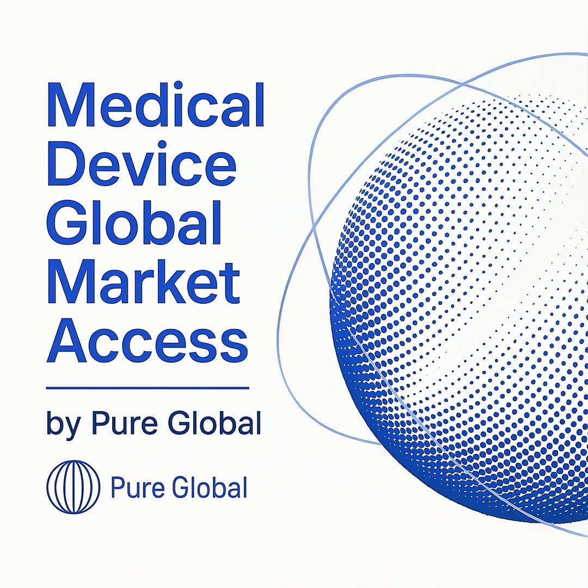The core of your submission is the technical file. This comprehensive dossier must include a detailed description of the device, its intended use, and specifications. You'll need to provide proof of a compliant quality management system, typically an ISO 13485 certificate.